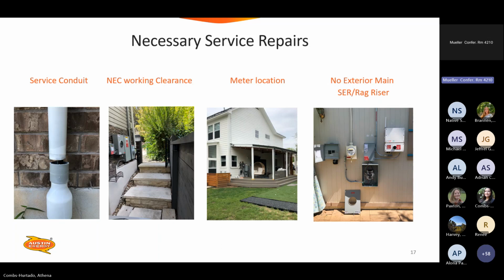That third picture, meter location, you can't see it that well, but you have a revenue meter underneath that porch, which is not acceptable to Austin Energy. So if you're selling a system and you see something like that, that is something that you have to handle before you can install the solar. You can see that solar was installed in there. So they installed the solar, interconnected, and then realized that they had to completely relocate the service. So it's better to spend the money in the right order and not do all that work before.